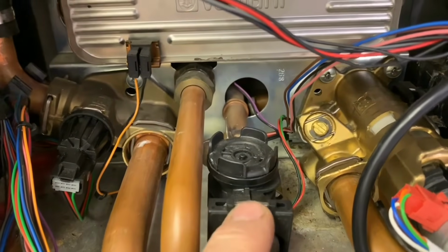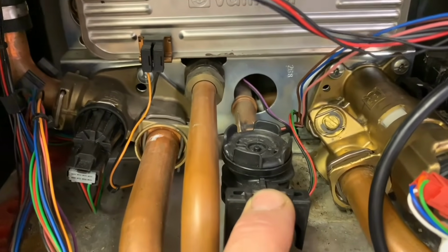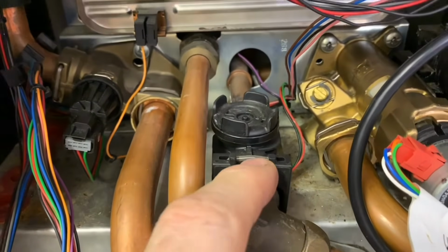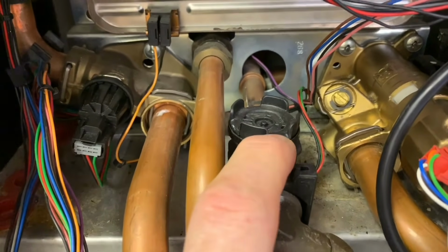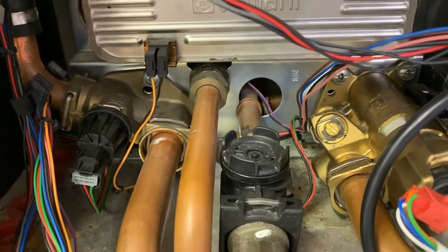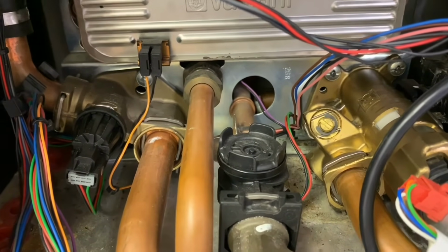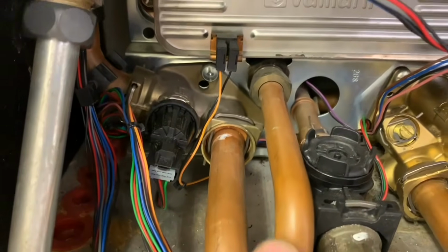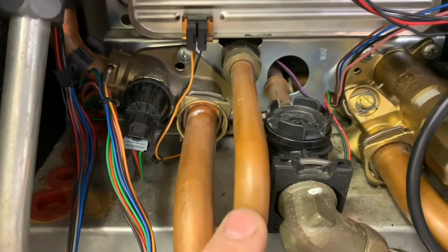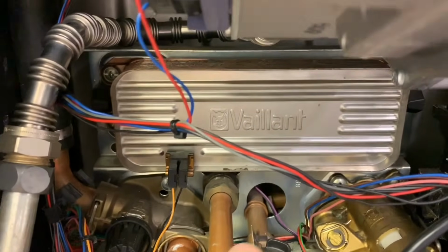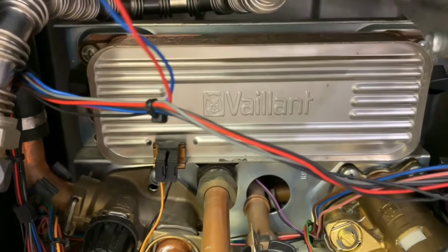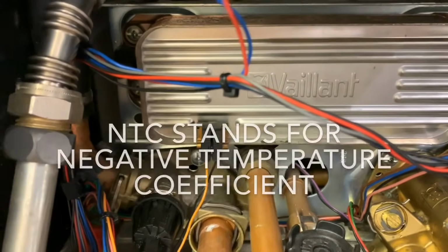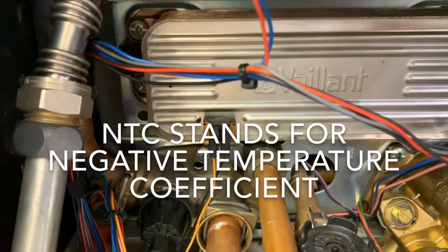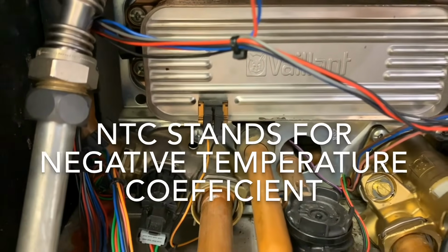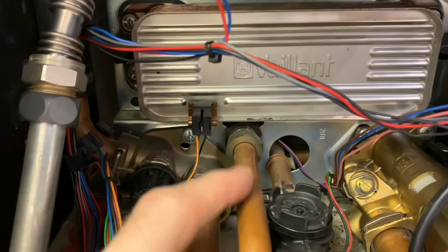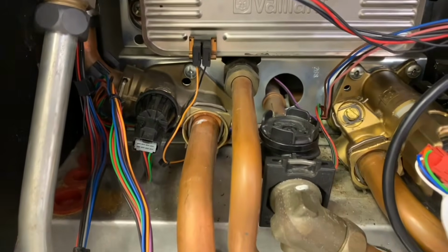So the next thing we've got along here is our cold water flow turbine. So cold water comes in here, makes a little turbine spin round with a Hall sensor, and the Hall sensor senses that the water's flowing and tells the boiler to fire up. Next one along is the hot water pipe. So that goes off to feed the taps from the plate to plate, because this big silver thing you see here is a plate to plate heat exchanger. Now this is an NTC thermistor which tells the boiler what the temperature is of the plate to plate. So they're in the Plus range. This is a Pro, but in a Plus range they have another NTC on the hot water out here.